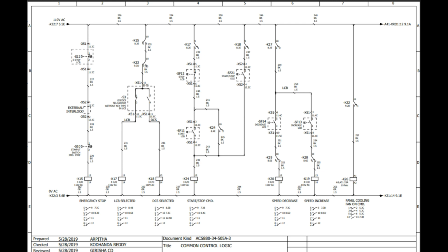If we need this, we will use it, else we'll put a loop, and it will get to another stop button that is provided on the panel. If both are healthy, both are not pressed, then K15, that auxiliary contactor, will actuate, and it is a signal that the emergency signal is healthy. Okay, we'll get to the second tapping. If K15 is actuated, the 110 volt supply, with the auxiliary contactor picked up, then K15 here, the second interlock, will get NC, and it will go through K23.